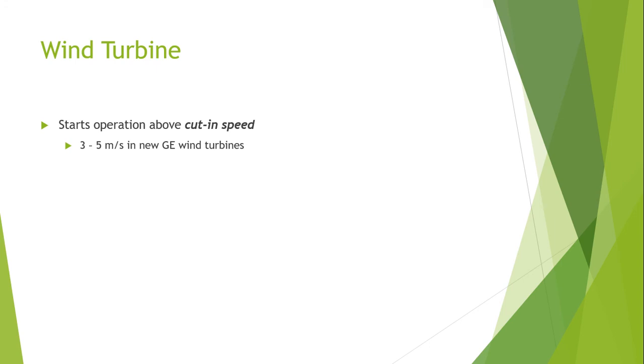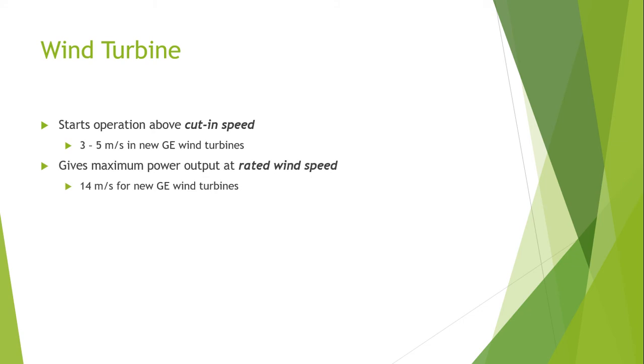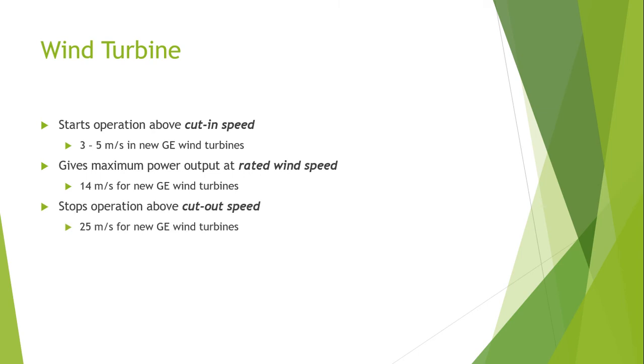GE Wind Energy is a branch of GE Renewable Energy, specifically for General Electric Company. This company manufactures and sells wind turbines to the international market. The windmill of GE company starts operating above the cut-in speed, around 3 to 5 meters per second in the new GE wind turbine. They give maximum power output at rated wind speeds of around 14 meters per second, and they stop their operation above the cut-out speed, defined at around 25 meters per second.